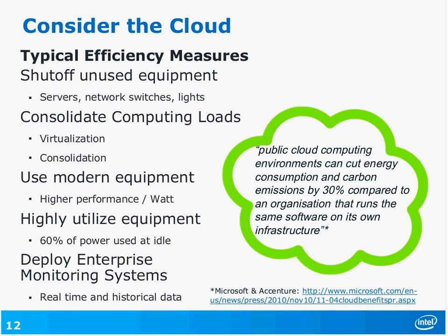As I mentioned, that notion of utilization. Very often in a typical data center, you'll see the majority of the servers being utilized at only 10 to 15%. Where people have done a lot of server consolidation, it might be better than that. But this is a really important metric because even modern servers still use a significant amount of power at idle. This bullet says 60%; that would be an older model server. We're making improvements on idle power as well as fully loaded power. It is important to remember that even when servers are lightly loaded, they are using power. So the extent that you can get utilization up, that'll be much more efficient.